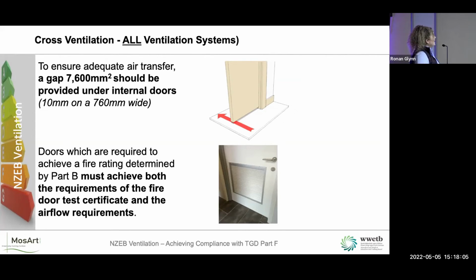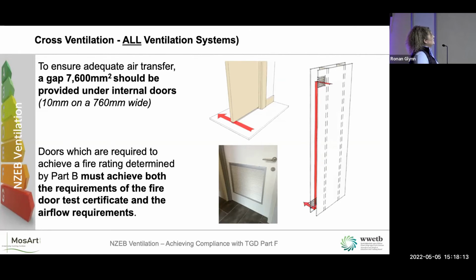So you can have a transfer air grill either. All right, so you can put intumescent mesh into that as well if you need it to be a fire door. You can also have a hit and miss vent. Sometimes a lot of noise transfers, maybe from a hallway into a bedroom or whatever. So if you use the hit and miss vents like this, this would be in your internal corridor, and that would be going into your habitable rooms then. And it just slows down the noise a little bit. Again, carpenters don't like those undercuts, so they've started putting overcuts in doors. So if you're doing an inspection and you don't see obvious undercuts, check the architrave for an overcut in the door as well.